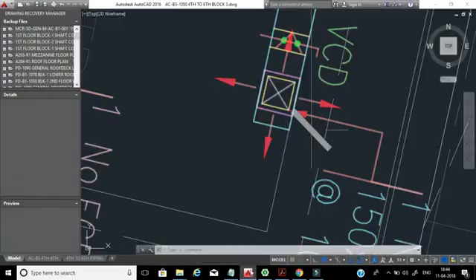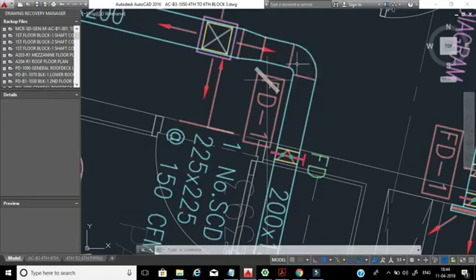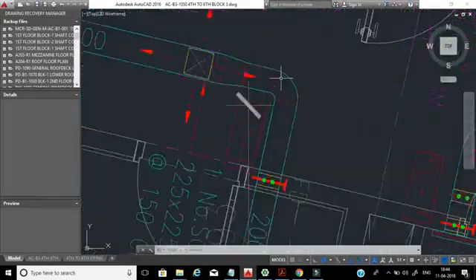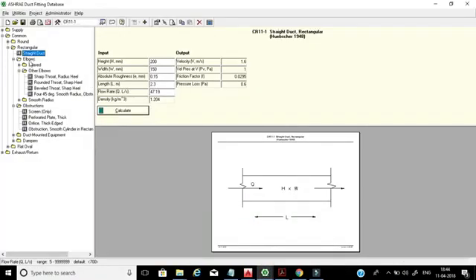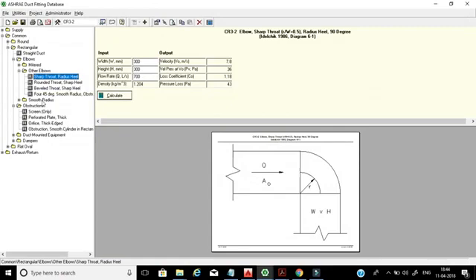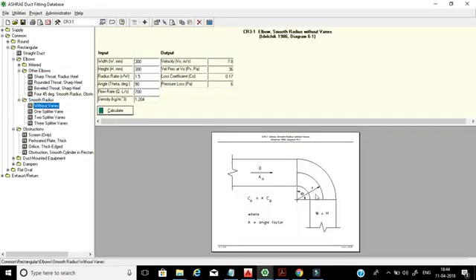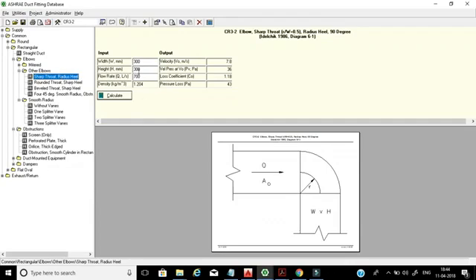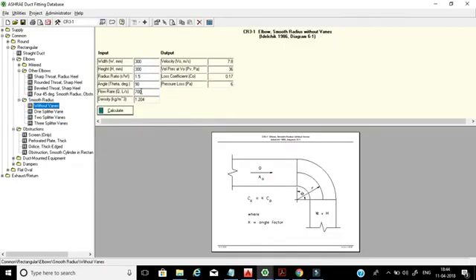Now I will show you one more fitting: for example, one elbow we have here in the drawing. This is a smooth elbow, and the duct size is 200 by 150. We need to calculate the friction loss for this elbow. All fittings are available in the ASHRAE Duct Fitting Database. For a smooth elbow, in the software you can enter the angle (90 degrees), radius, and flow rate. Once you enter those values, the pressure loss will be calculated automatically.